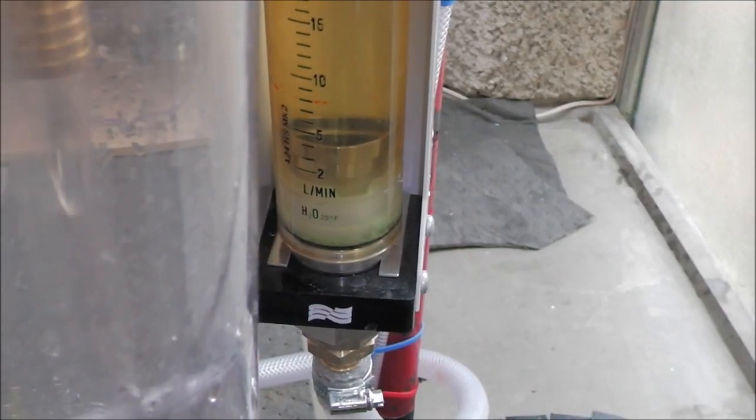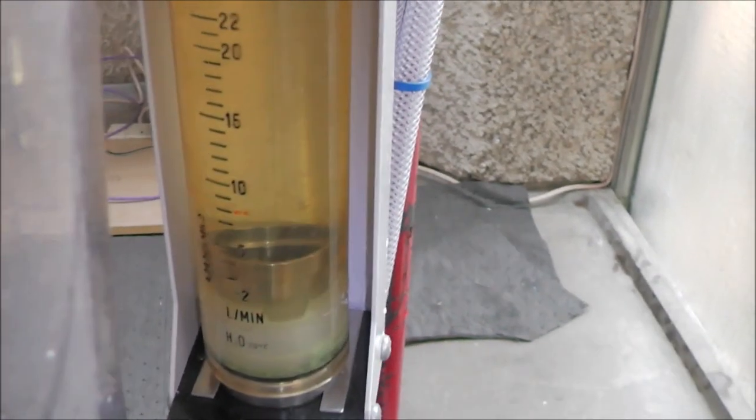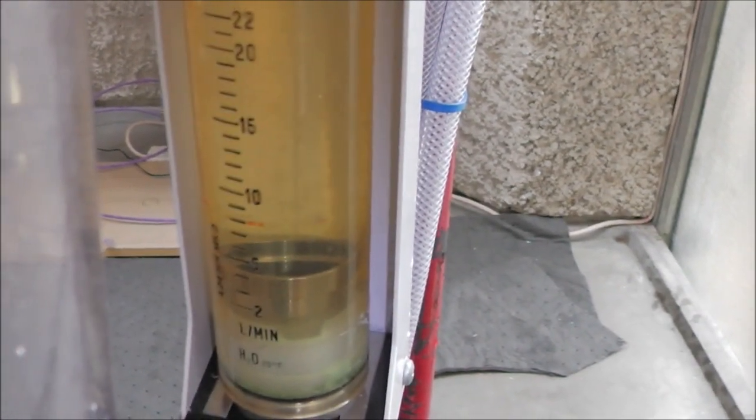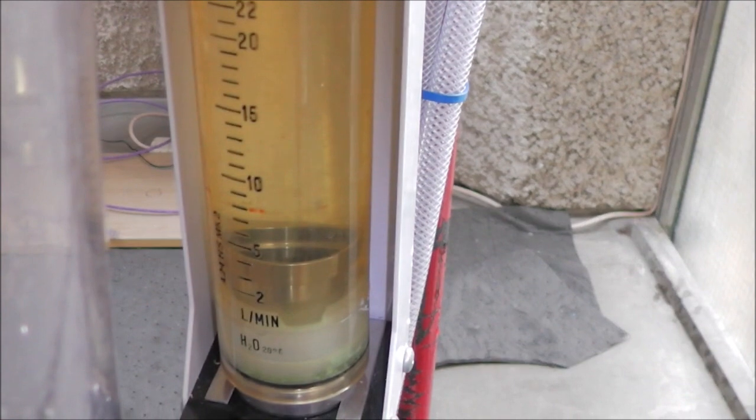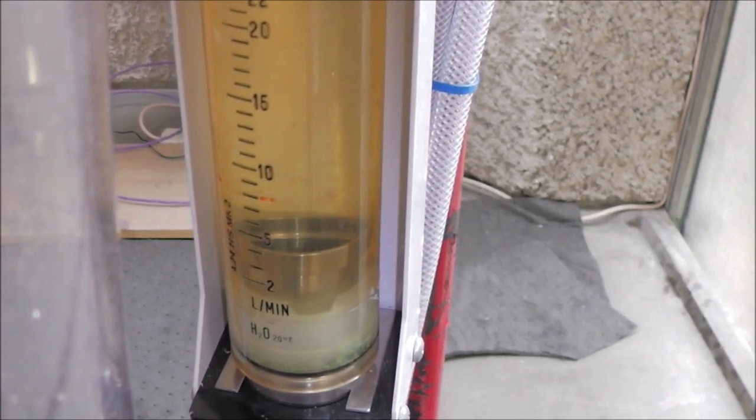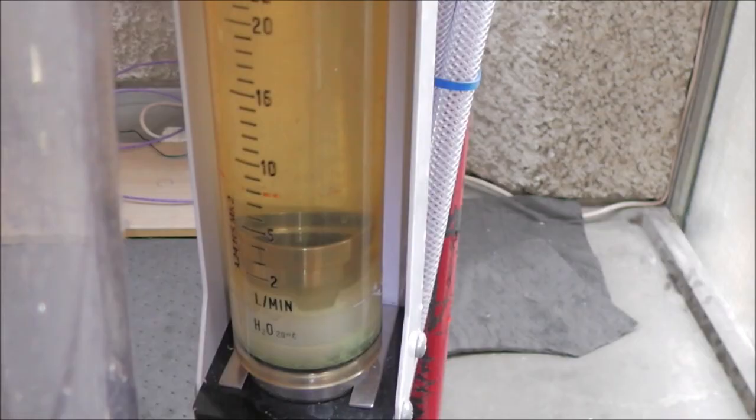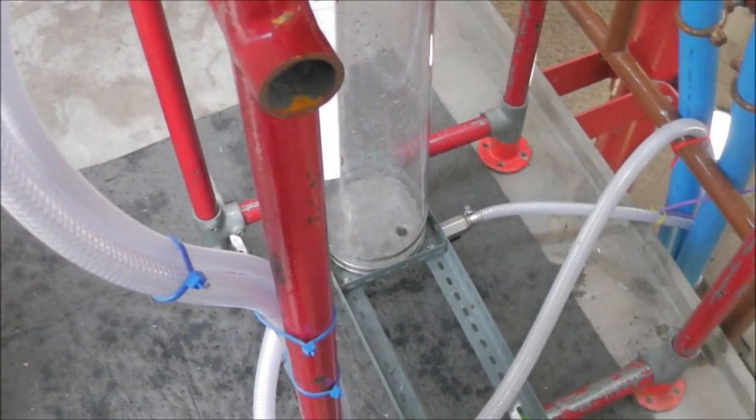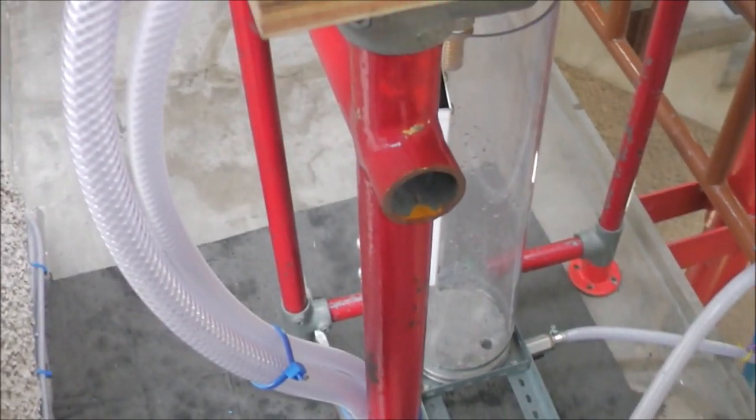A rotameter measures the flow rate. Here we are pumping at around 4.5 liters per minute or equivalently 270 liters an hour. This can be increased significantly by either driving the DART pump harder or by decreasing the head to which it is pumping to.